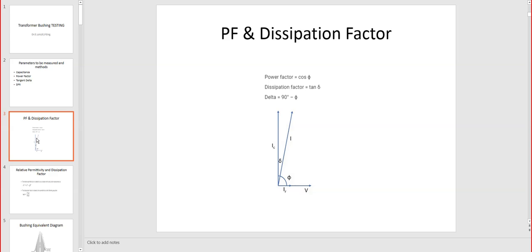This is a very important slide, telling us what power factor and dissipation factor are. The total current has two major components. One is resistive, one is capacitive, and those are actually forming those two angles. The power factor is the cosine of the angle, Greek letter phi, between the resistive leakage current and total current. That's dividing the resistive component by the total leakage current. You get the cosine of the phi angle, which is the power factor, somehow similar to what we know from electrical circuits, but that's between current and voltage per phase. Here we talk about components of the total leakage current, the component on the resistive side.